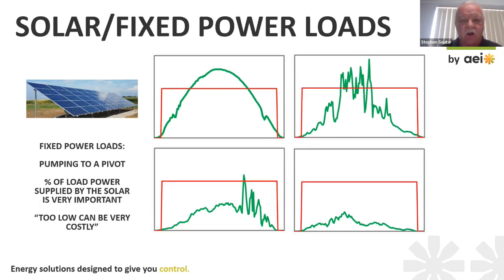You just get what you get. So when you put solar with fixed power loads, an example of that is pumping to a pivot. The load doesn't have to be perfectly constant, it just means you don't have control over what the load is and it remains fairly steady. So the percentage of load power supplied by the solar is very, very important.